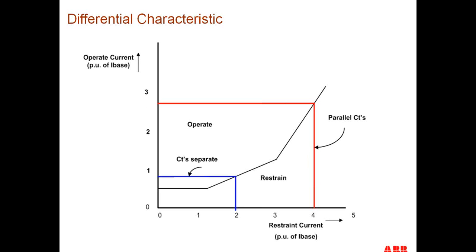If I kept each of the CTs separate, remember I'm using the largest of the currents in each one of the phases for my restraint current. If I keep the CTs separate, then I only have 2 per unit current as my restraint current, and my operate current based on a 2 per unit restraint current is only going to be slightly over or slightly less than 1 per unit current. So I'm gaining much sensitivity by keeping these two current transformers separate.